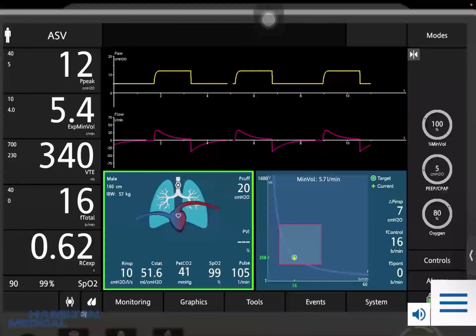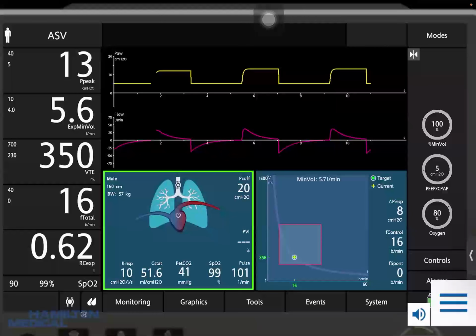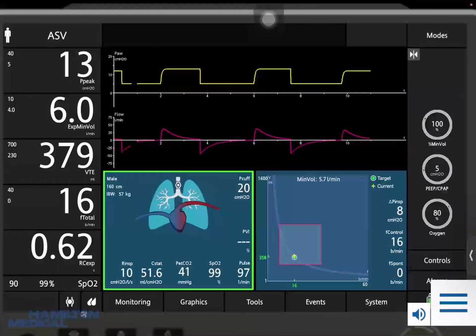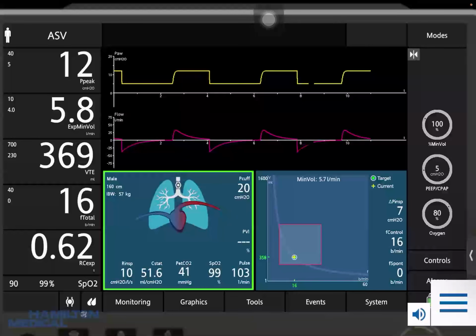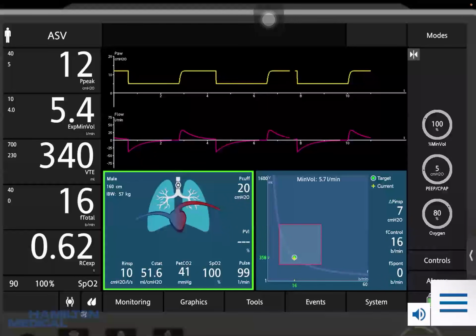All right. So that is basically we get the information from the patient. So that is sort of a pressure regulated volume control like. So anyway, but it's more complex than that, because they use certain equations to get that optimal respiratory rate and the expiratory time constant. Okay, so the patient and machine deliver, and the inflation pressures are adjusted according to the patient response.